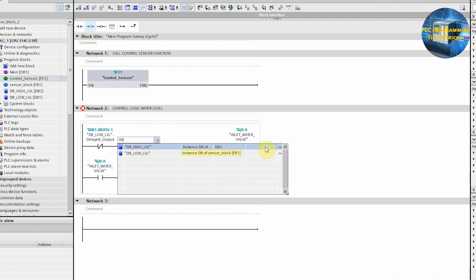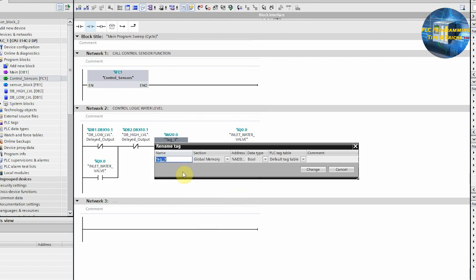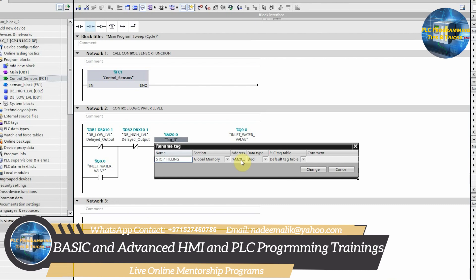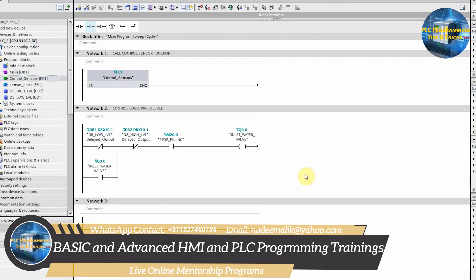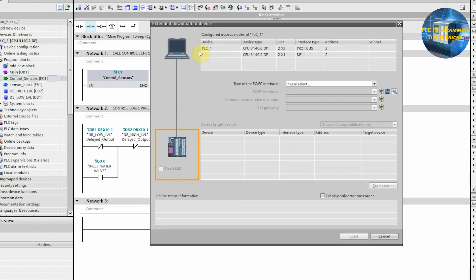Next, we will insert a normally closed contact and assign it the high level delayed output tag, so that when the water level reaches the high level sensor, this contact opens and turns off the Q0.0 output. Next, we will insert a normally open contact M20.0 — this is the stop filling bit — which will stop the filling at any moment. Our programming is now completed.